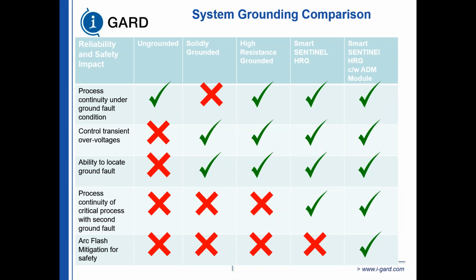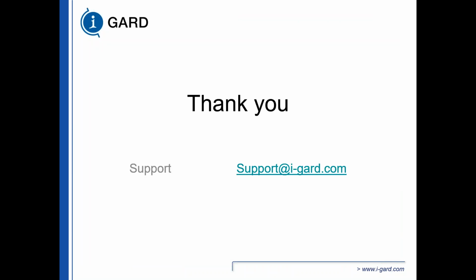The Sentinel with HRG with arc flash module is going to give you everything. It's going to give you the process continuity with the second ground fault and arc flash mitigation, because we have the arc flash relay in here. With the Smart HRG, without that module, you're not going to have the arc flash mitigation for safety. So we went from 6 on this one, and this one I believe was a 10 on the safety meter. And with that, I'm going to turn it over to you guys.